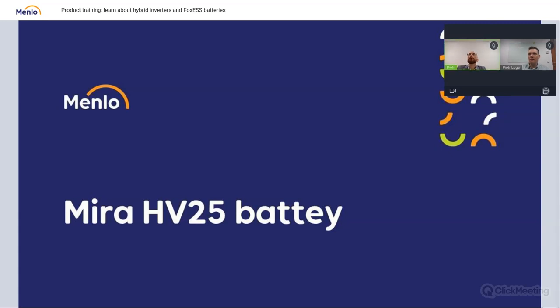Yeah, sure. It's possible. It's a standard operation for that unit. It's designed for doing that. So, concerning the state of charge needed for the battery to, let's say, live and not die, not decompose the chemistry inside, the BMS will always check and provide enough charge in the cells automatically. So the minimal charge amount of the battery is 5%.